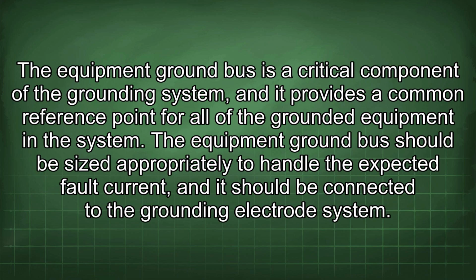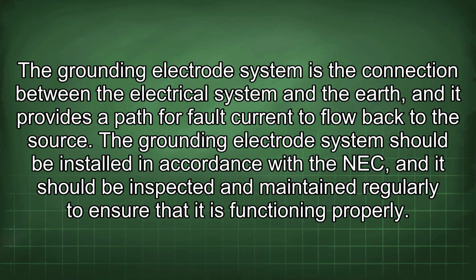The equipment ground bus is a critical component of the grounding system, and it provides a common reference point for all of the grounded equipment in the system. The equipment ground bus should be sized appropriately to handle the expected fault current, and it should be connected to the grounding electrode system. The grounding electrode system is the connection between the electrical system and the earth, and it provides a path for fault current to flow back to the source. The grounding electrode system should be installed in accordance with the NEC, and it should be inspected and maintained regularly to ensure that it is functioning properly.